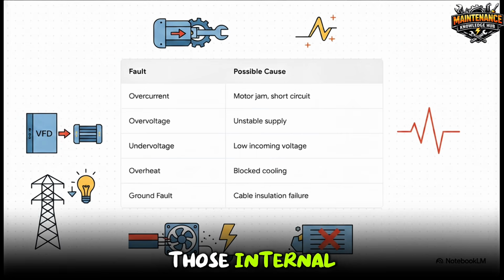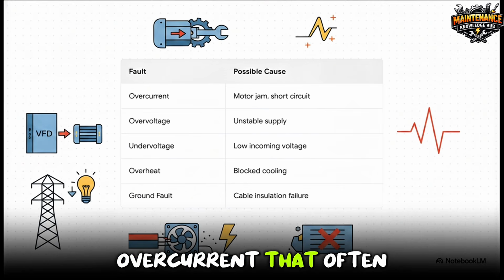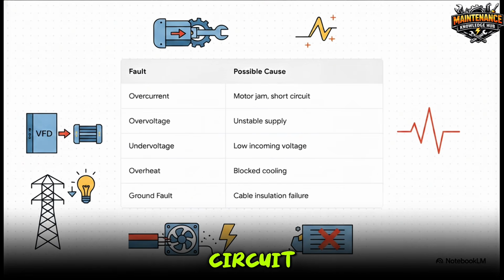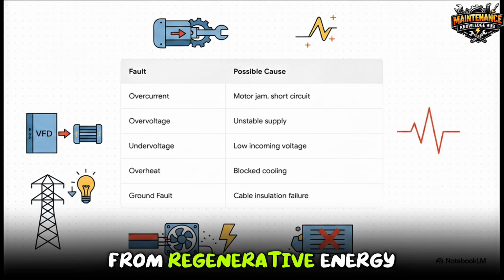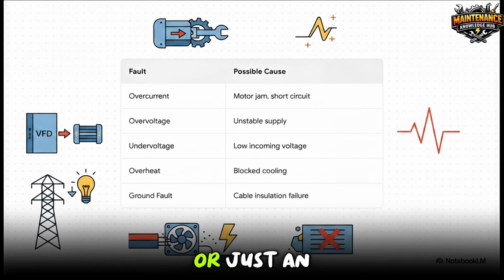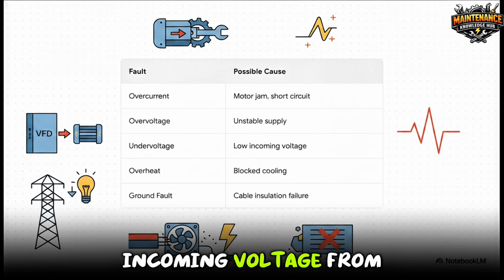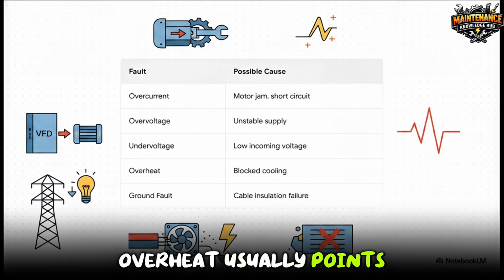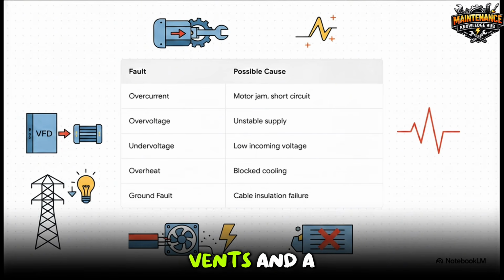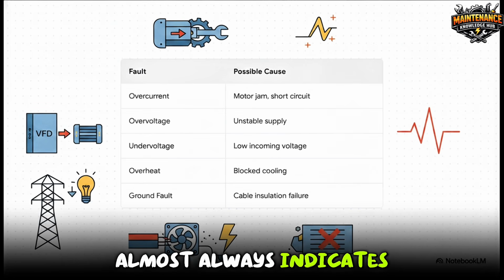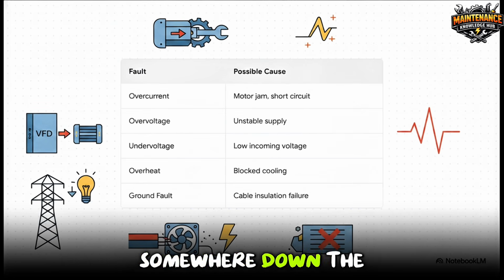Here we can tie those internal protections directly to the common faults a technician will actually see flashing on the display. Overcurrent? That often means a physical motor jam or a short circuit. Overvoltage can happen from regenerative energy pushing backward from the motor, or just an unstable power supply. Undervoltage simply means low incoming voltage from the grid. Overheat usually points to a dirty fan or blocked cooling vents. And a ground fault almost always indicates a cable insulation failure somewhere down the line.